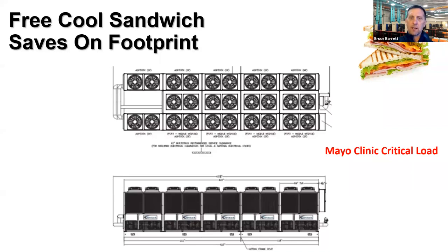Our 30 ton and below, since we draw the air from the face and the base of the module, we can also slide those modules up next to a wall. And then you can duct out your discharge line above the roof edge. So that's a great footprint saver. You don't need 6-8 feet all around that chiller. We can get creative when it goes into a chiller yard with a wall or even a building right next to the chiller.